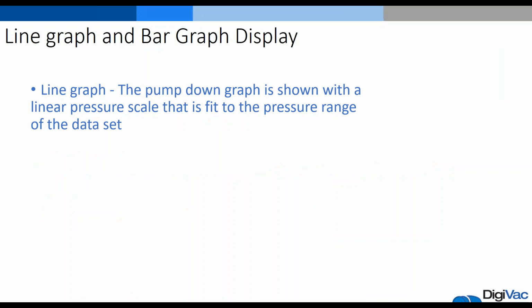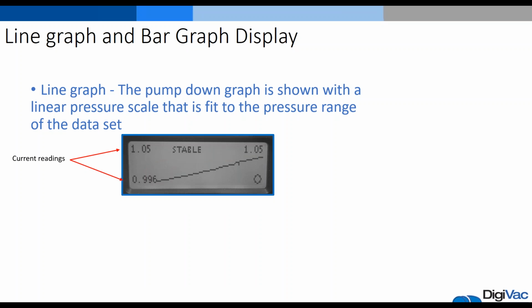And then the line graph and bar graph displays that are available on the Bullseye. The line graph is the pump down graph that is shown within a linear pressure scale that is fit to the pressure range of the data set. And you can see that by looking at the numbers in the upper and lower left-hand corners to see where the pressure started and where it ended up. Sorry, I apologize, I said right-hand before. In the upper left-hand corner you can see where it ended up with 1.05, and that would mean that this system is stable.